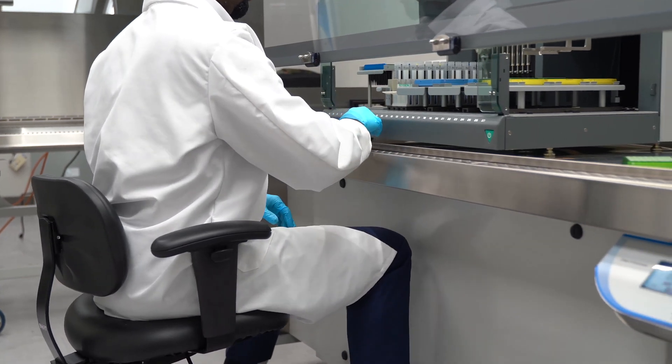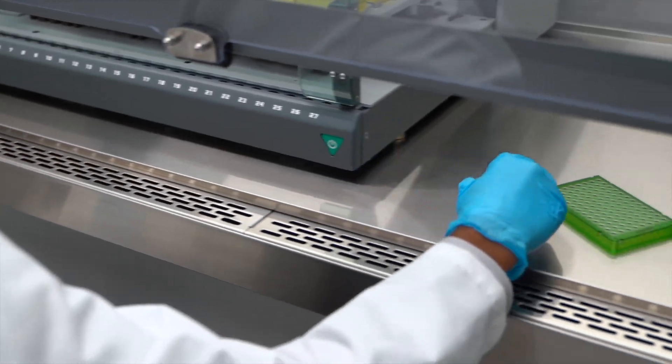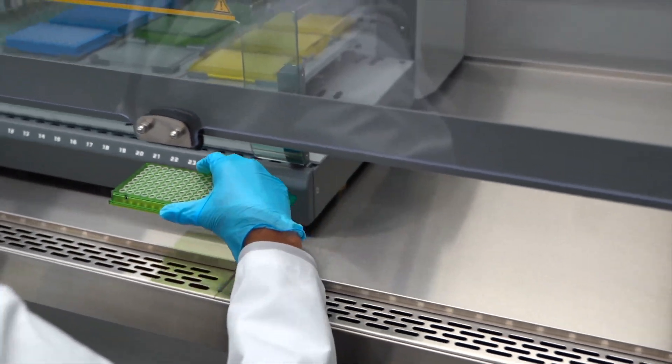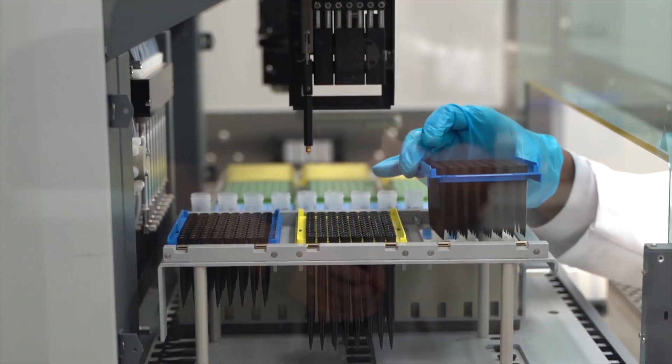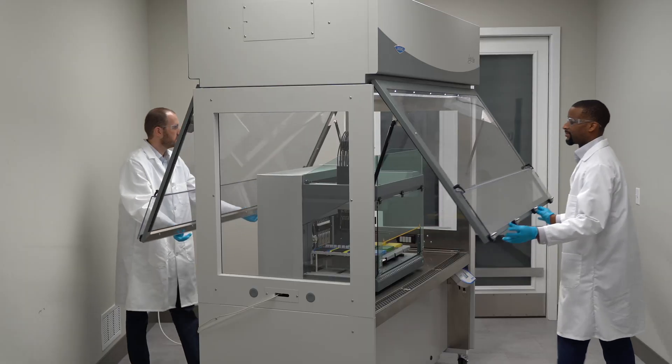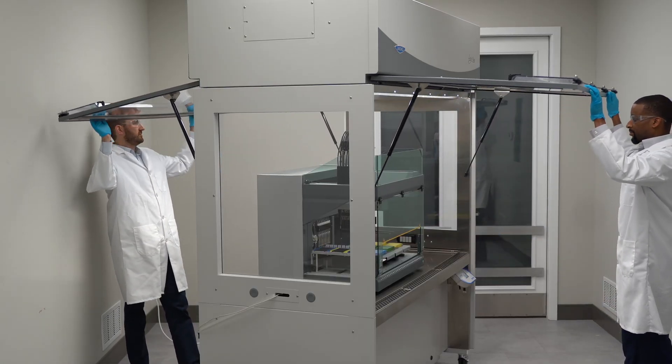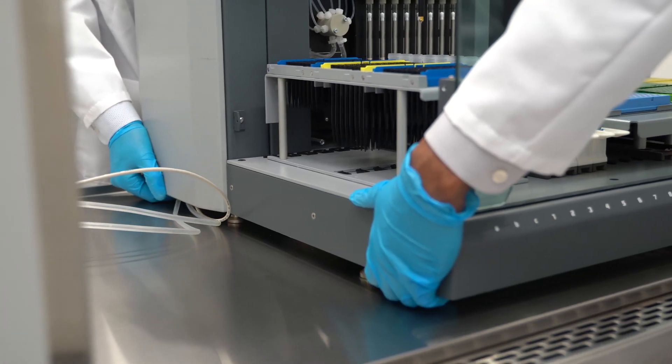Its lower sashes provide unobstructed access to the entire work area for safe manipulation of equipment and samples. This partition-free design allows free movement across the sash opening. Open the large upper sash panels to access your equipment for setup and maintenance.